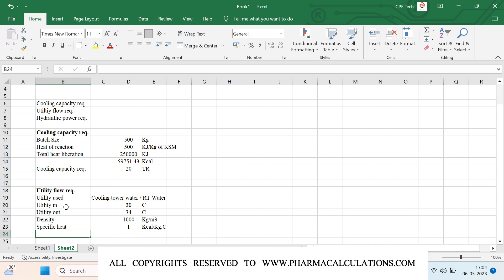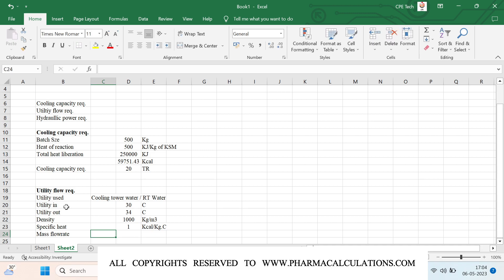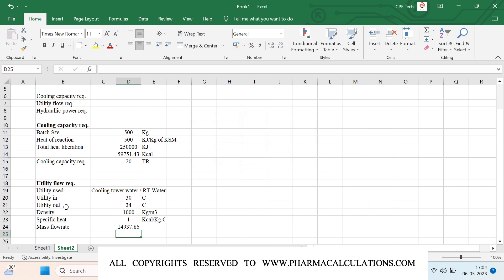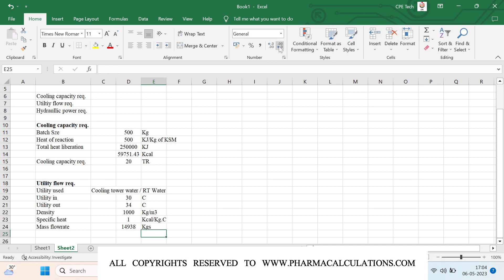From these values, we calculate the mass flow rate. Mass flow rate equals total heat liberation — 59,751.43 kilocalories — divided by Cp times delta T. Here Cp is 1 and delta T is 34 minus 30, which equals 4 degrees. This gives approximately 14,938 kg of utility flow required in total.